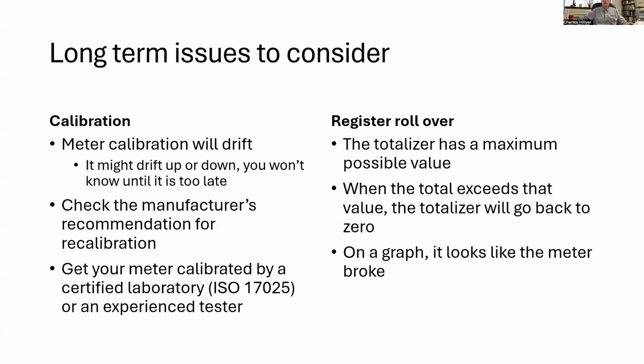This recalibration is important because as the meter drifts, it might drift up and it might drift down, and you won't know until it's too late to do anything about it. So following the manufacturer's recommendations about calibration is essential to make sure you don't run into this problem where somebody says, Joel, your meter is under-reporting and you actually pumped a lot more than that. Also, when you get your meter calibrated, make sure you either get it tested or calibrated at a certified laboratory. So the thing you need to look for is, is the laboratory ISO 17025 certified? That's a laboratory certification that guarantees that they're doing a good job and that they keep all the records that are necessary to prove that they're doing a good job.